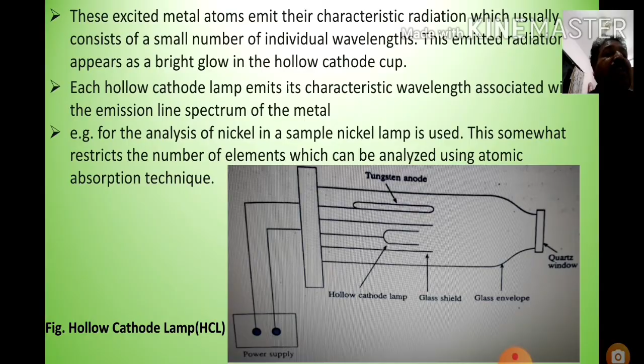This somewhat restricts the number of elements which can be analyzed using atomic absorption technique. This is the figure of the hollow cathode lamp, which includes the anode made up of tungsten, and a hollow cathode cup that is made up of the element which is to be tested.